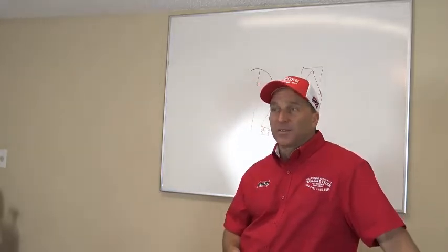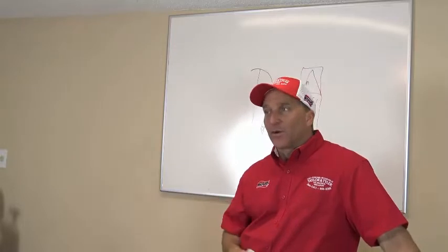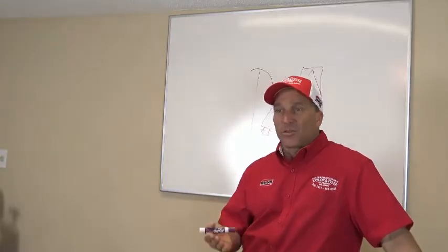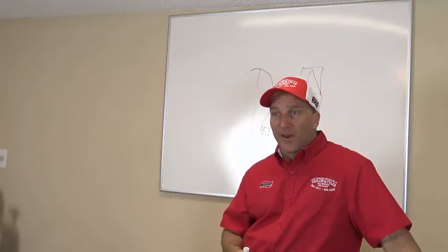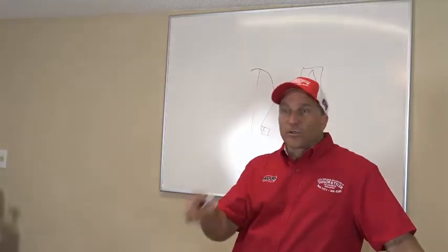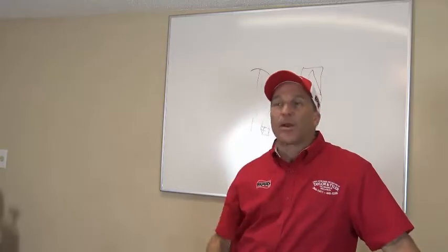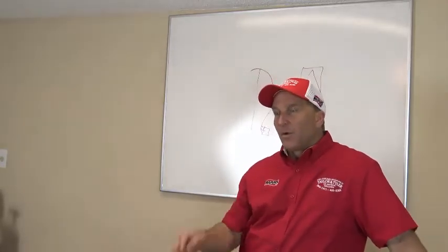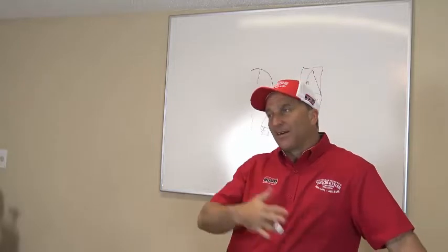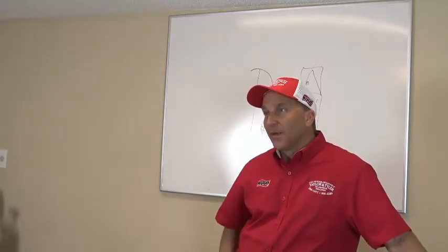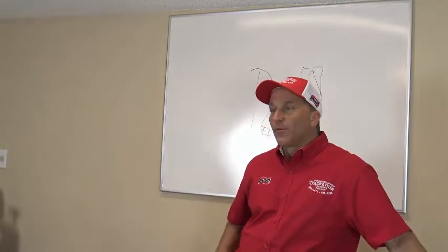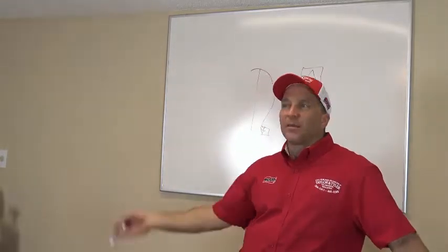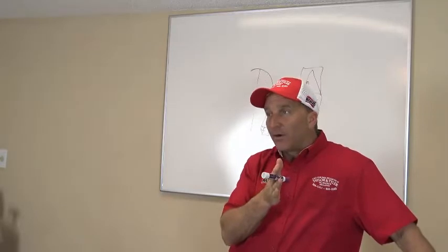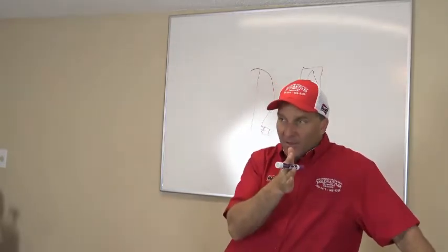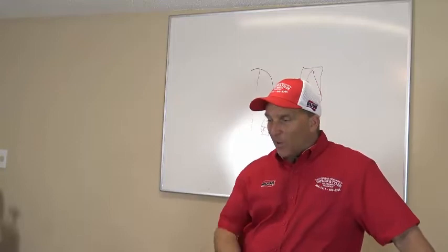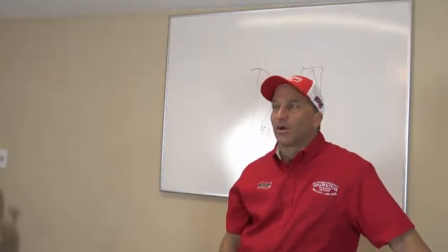A lot of times. And when you go there, especially on a service call, on an install, we're going to replace it, so we better install it properly, right? We better make sure that the holes are cut out big enough so that you get the proper airflow through the system, okay? But on a service call, you're going to everybody else's, okay? Let's make sure we do the right job by looking from the return grill all the way to the back of the heater. Your return is from the back end of the heater to the return grill and anywhere in between that chase. That is your return plenum.